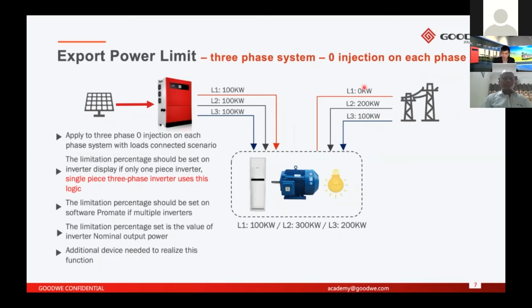And this one is the zero injection on each phase. This is actually a very, very special case. It only happens in some small countries like the Czech Republic, because the grid company measures the power on each phase. Unlike other countries, where the grid company measures the consumption on the three phases in total, in the Czech Republic the grid company measures the power on each phase, and they send the electricity bill to the customers also according to the consumption on each phase. So that's why the customers there ask for this function, zero injection on each phase.